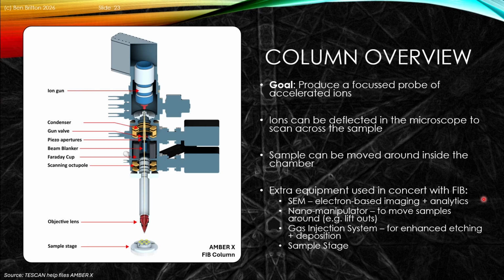Now there is a range of extra equipment that will be used in concert with the FIB column. We're going to heavily use a scanning electron microscope and the associated analytics such as the ETD detector. We might also have a nano manipulator to move samples around, for instance when we're doing a lift-out operation. We're going to have a gas injection system, a GIS, that enables us to enhance etching and deposition depending on the precursor gas that's present. And I've already mentioned the value in the sample stage that's presented in the microscope.